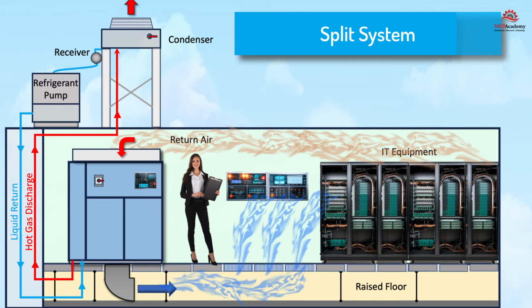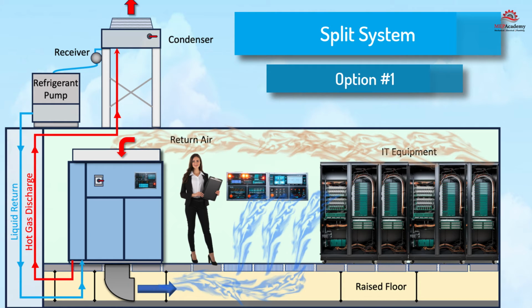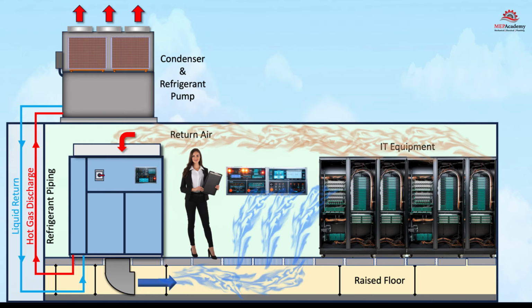Split system. The first option is the use of a split system where the condenser sits on a stand on the roof. There is an additional piece of equipment that houses the refrigerant pump. A refrigerant receiver collects liquid coming from the condenser and feeds it to the refrigerant pump. During economizer mode, the pump will circulate the refrigerant while the compressors are off, or during mixed mode, both could be operating on separate circuits. There is also the option to have the refrigerant pump housed with the condenser, but the operation is the same.